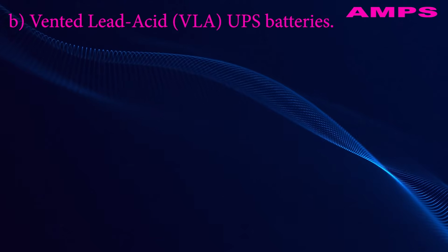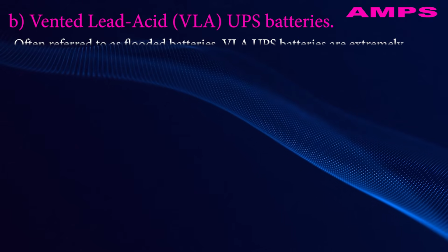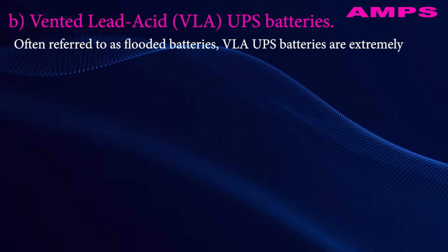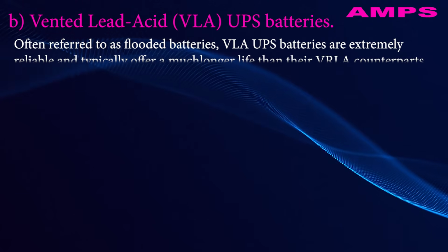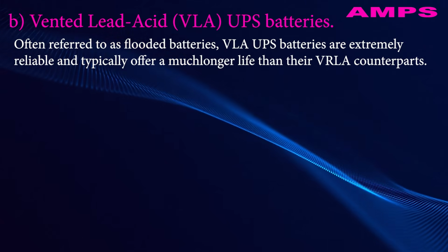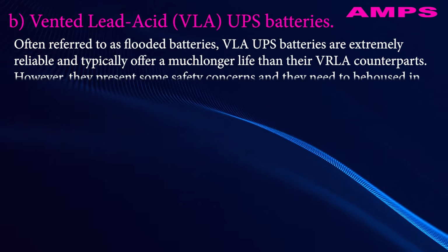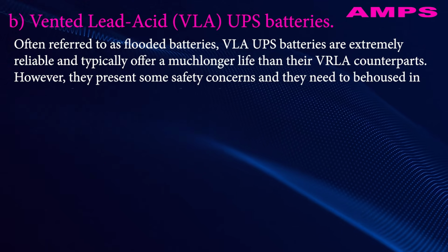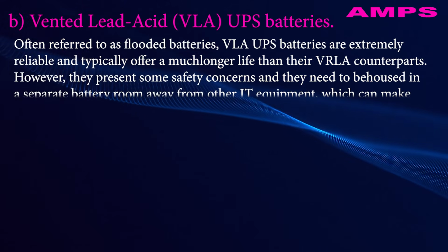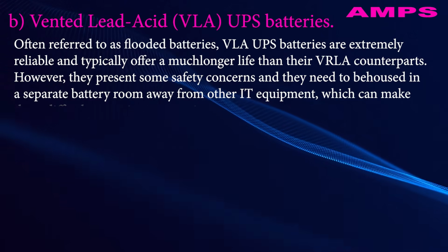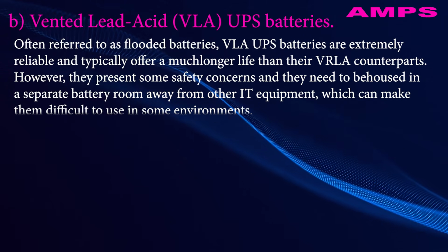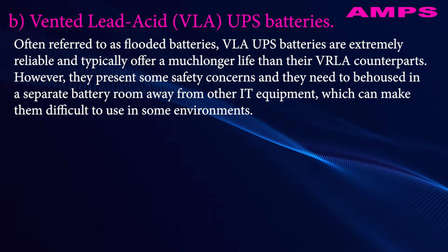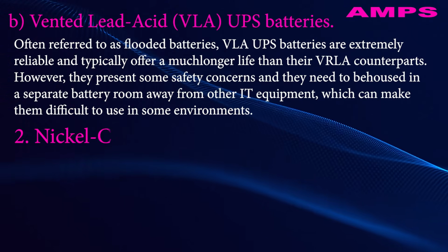b) Vented lead-acid, VLA, UPS batteries. Often referred to as flooded batteries, VLA UPS batteries are extremely reliable and typically offer a much longer life than their VRLA counterparts. However, they present some safety concerns and they need to be housed in a separate battery room away from other IT equipment, which can make them difficult to use in some environments. 2.